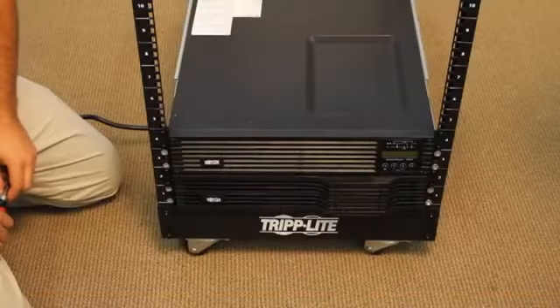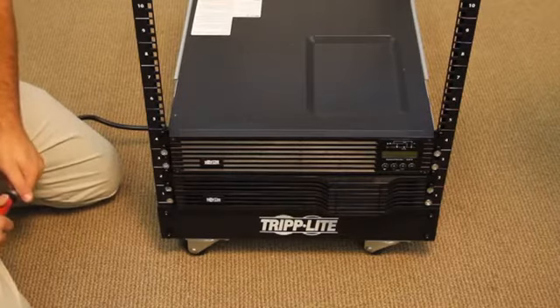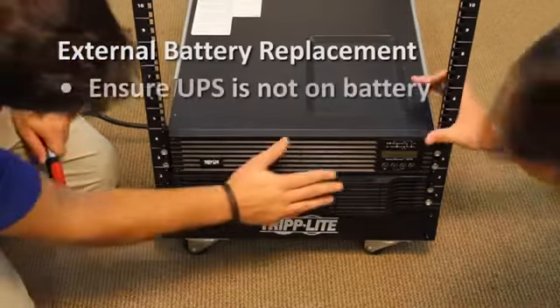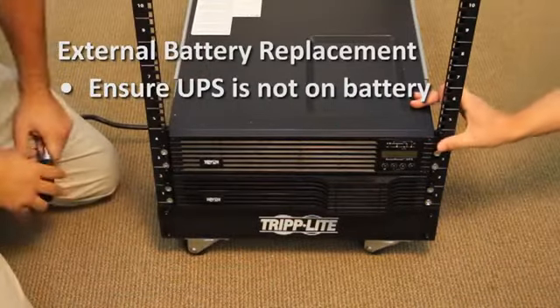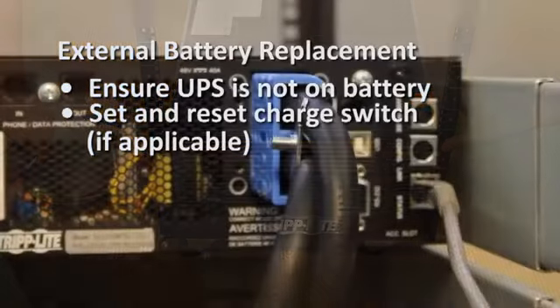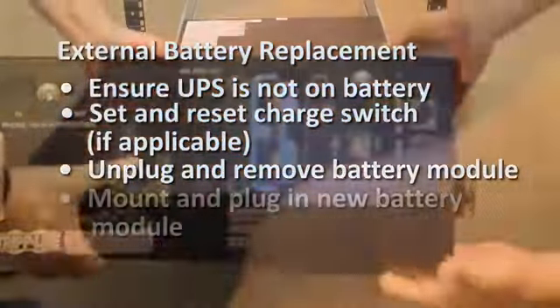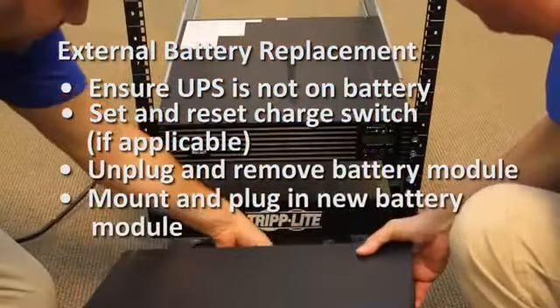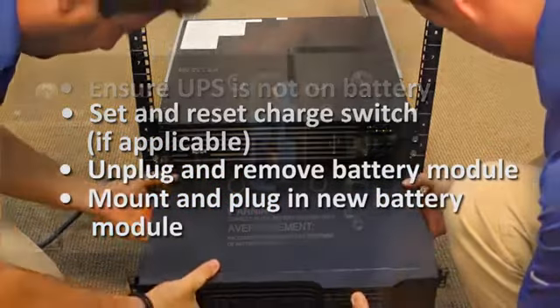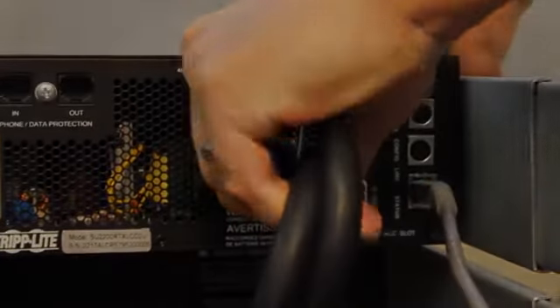All UPS systems accept one or more external battery modules. To replace these, use several assistants — battery modules are very heavy. Ensure the UPS is not operating from battery power. Set the battery charge switch, if your model features one. Unplug and remove the battery module. Mount and plug in the new battery module. Reset the battery charge switch if your model features one. Note: small sparks may result during battery connection — this is normal.